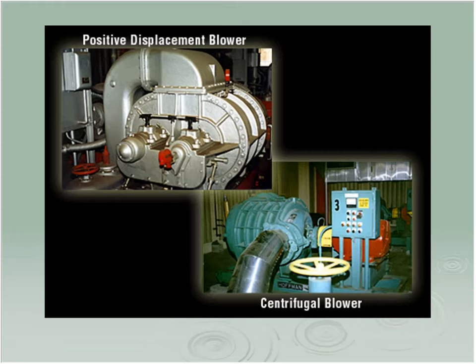Today, most plants are using things like positive displacement blowers, a Roots-type blower, or you can use a centrifugal blower. The difference being, see those first two words there, positive displacement? That means something's going someplace. Don't close the valve, unless you want a bad day.